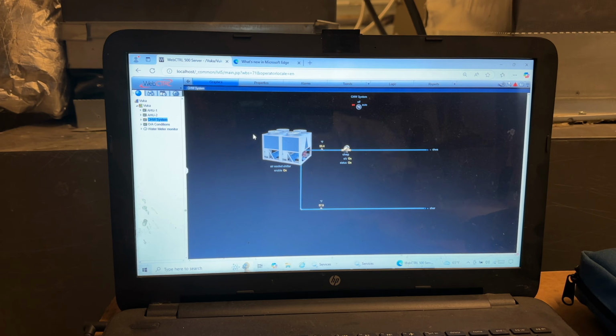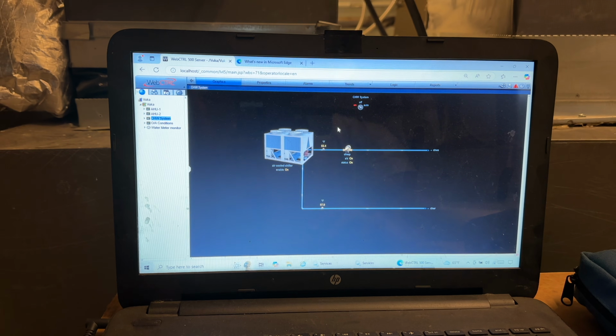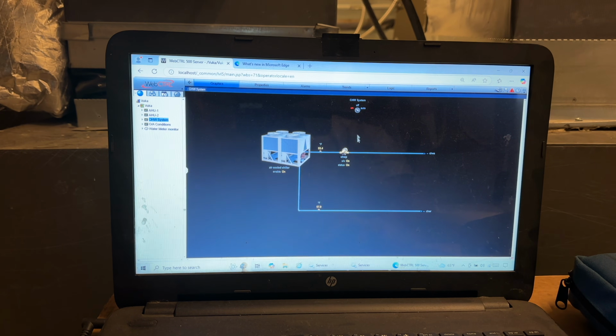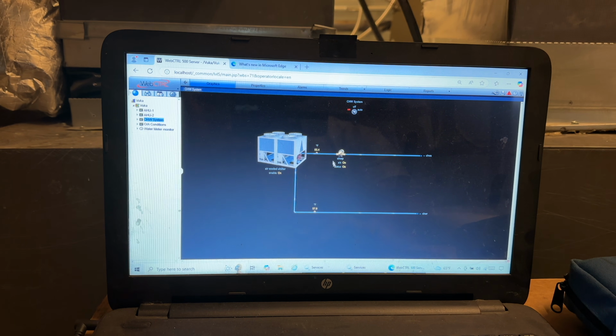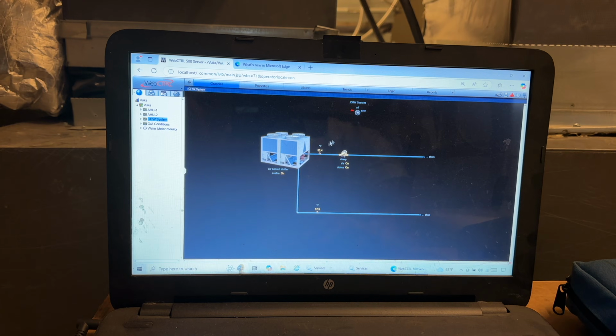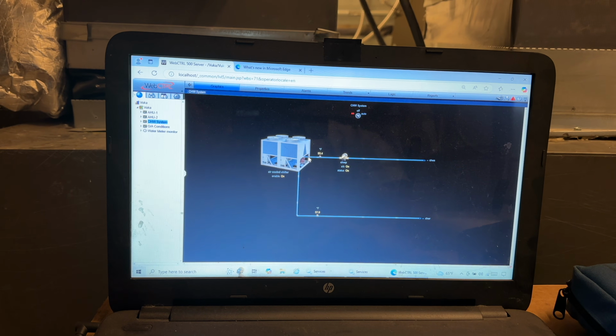Whenever I logged into it, I saw that the pump was in the off position. I'll show you right now. So after about 5 minutes, the first time that I logged in, it was showing that this water pump, this chill water pump, was off, and the system was in alarm because of the pump being off.